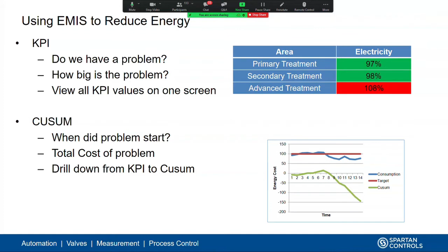So as you can see on that graph on the lower right hand side, that green trend, there's an inflection point at around the 7th period that shows us at that point our energy consumption was much higher than our target energy consumption, which gave us that negative trend. So we know at that inflection point, that's when it began. Now we can go back in history to that same time to troubleshoot and figure out what happened at that time to cause this high energy consumption. Those types of rudimentary tools are included in your standard EMIS.